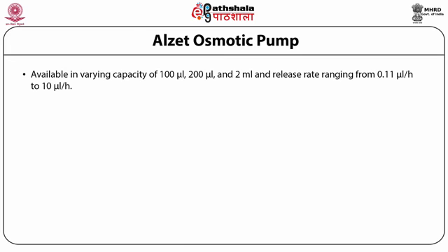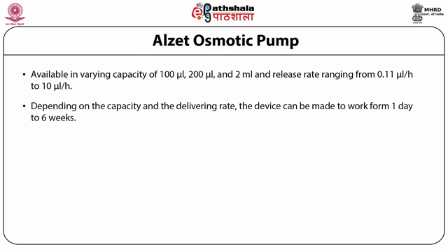The pumps are available in varying capacities of 100 microliters, 200 microliters and 2 ml, and release rates ranging from 0.11 microliters per hour to 10 microliters per hour. Depending on the capacity and the delivery rate, the device can be made to work from 1 day to 6 weeks.